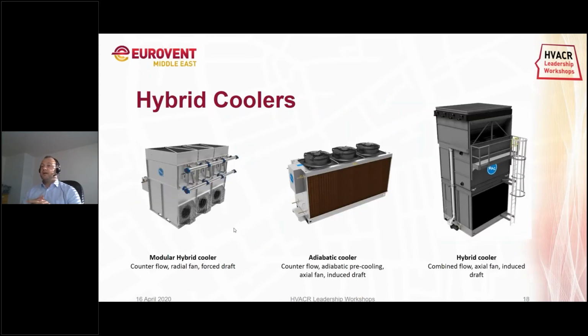And then the last group that we see are the hybrid coolers. We already discussed the modular hybrid cooler, and besides that, there is also an adiabatic cooler. That works most of the time dry. And if the ambient temperature increases and the capacity cannot be reached, it can work in wet operation due to the adiabatic pads. Next to that, we also have a regular hybrid cooler that can have a wet and a dry coil separately. It can reduce the water consumption by 70% compared to a normal fluid cooler. So you see, there are different solutions for different needs in the project.